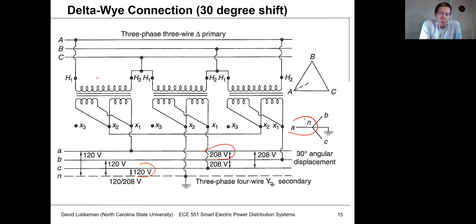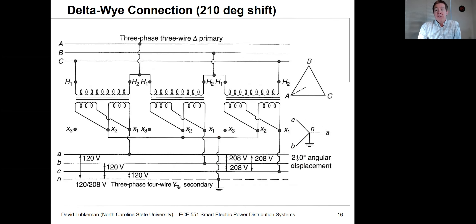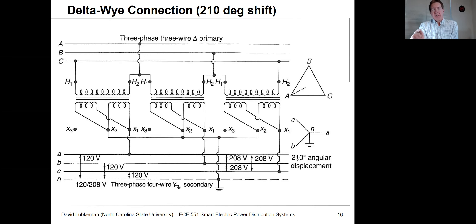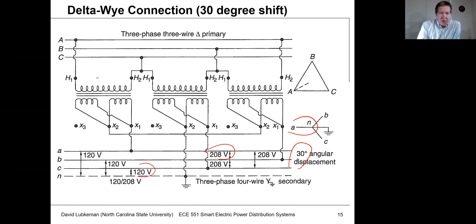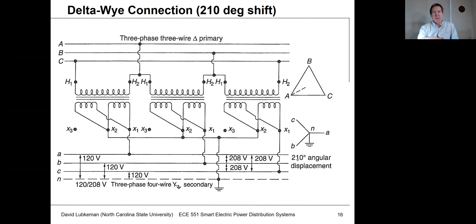This phase shift is not something we model or worry about if you just have a single transformer, but it becomes a problem if you have two transformers in parallel. One transformer might give a minus 30-degree phase shift, and another might give a 210-degree phase shift — making the two secondaries incompatible if you try to parallel them. You have to be very careful about how you connect these transformers up. The only apparent difference between two diagrams may be in how the primary is connected, and a simple wiring mistake would change the phase shift relationship.